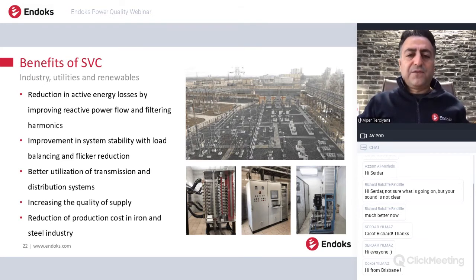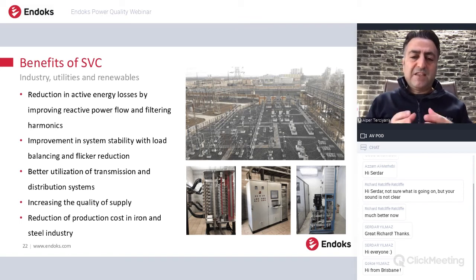And the benefits of the SVCs. SVCs are mostly used with big loads. I mean the mining industry, cement industry, iron and steel industry, all these industries, because the SVCs are big systems, and it can be used with these type of loads, and there's a reduction in active energy losses because of improving reactive power flow and filtering the harmonics. So these are the main benefits of the SVCs.